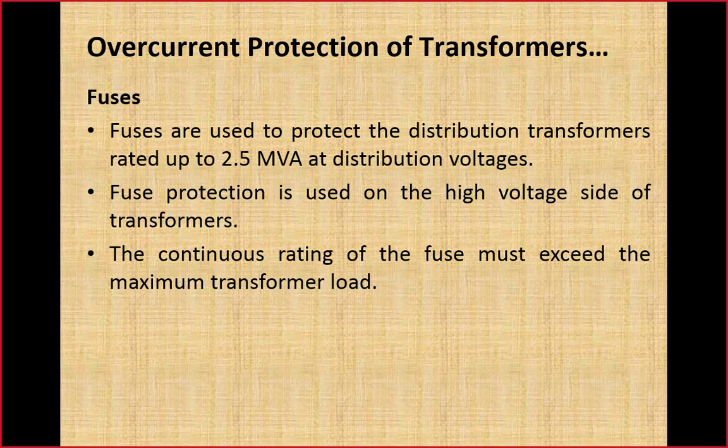The continuous rating of the fuse must exceed the maximum transformer load. So it means the fuse should not get interrupted or blown off due to the normal loading current of the transformer. This is the first requirement of the fuse.